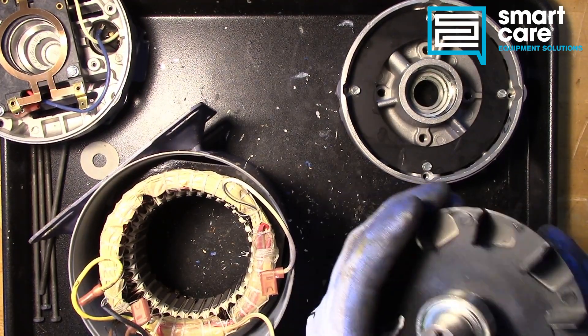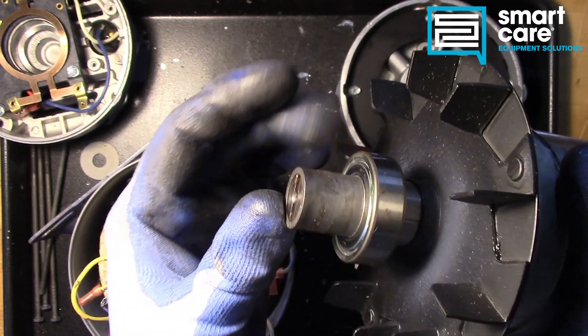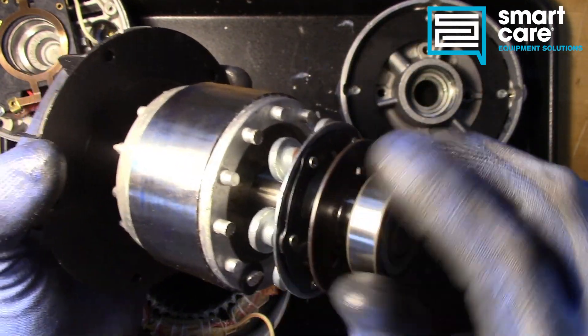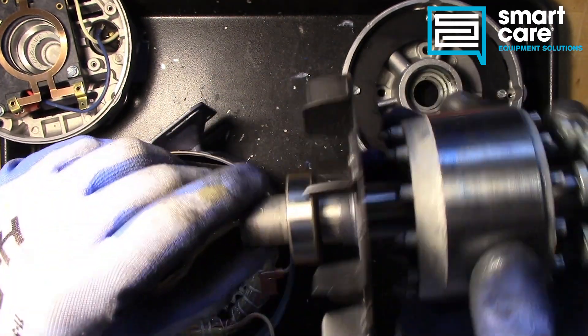You can see there's a cooling fan here. And there's our front bearing — front bearing is still very good. And our back bearing is still very good. There's no noise or friction when I rotate them. So really it's not looking too bad.